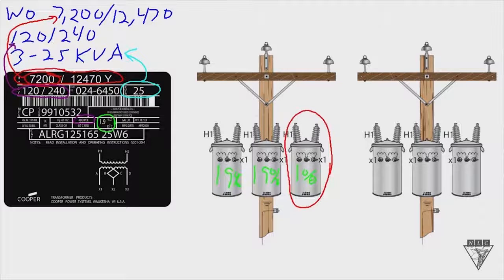A good way to indicate that it's additive polarity, besides the transformer nameplate, is if we look at our transformers that are banked, if the X1 bushing is on the right-hand side, then they're additive polarity. If the X1 bushings are on the left-hand side, then they're subtractive polarity, like this one on the far right.